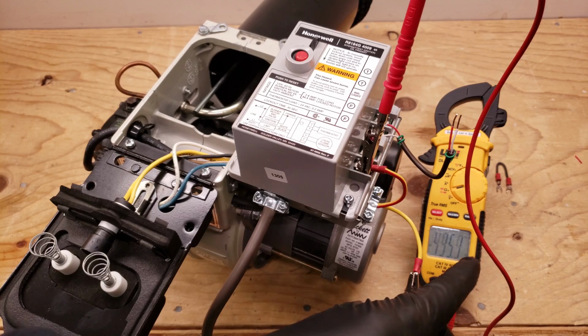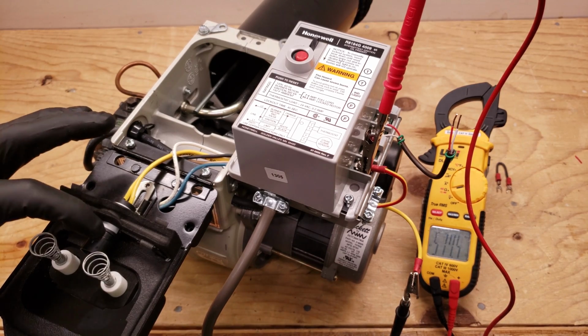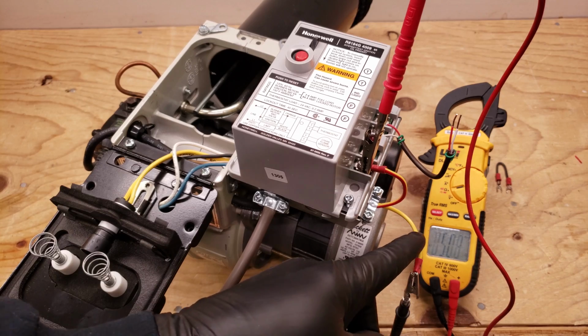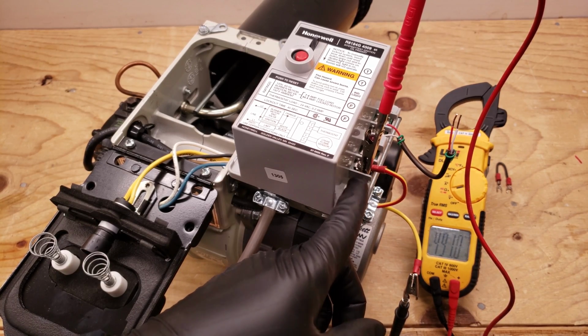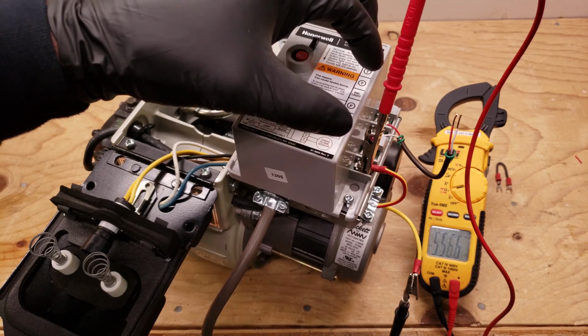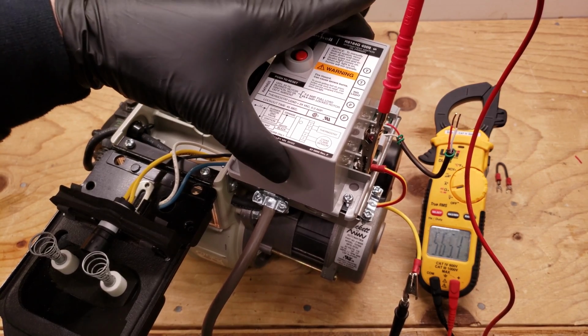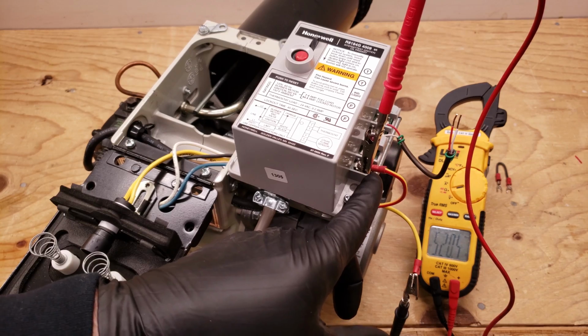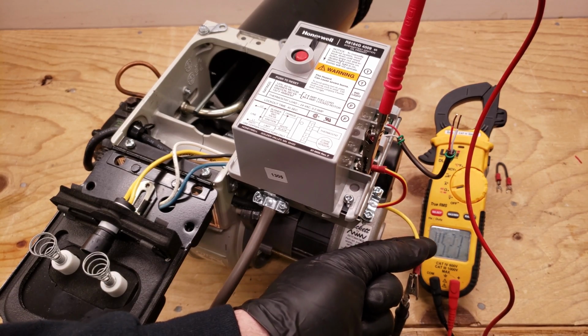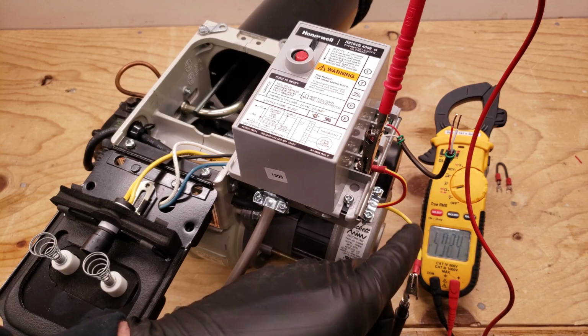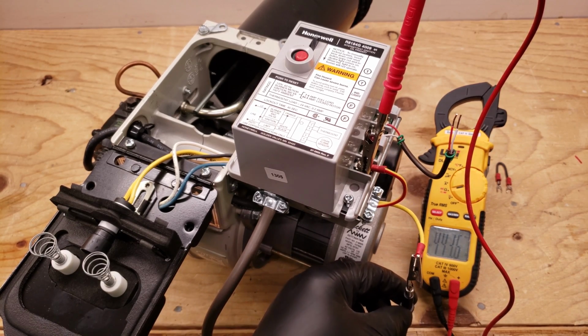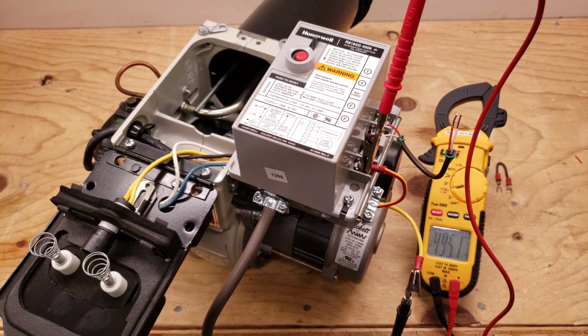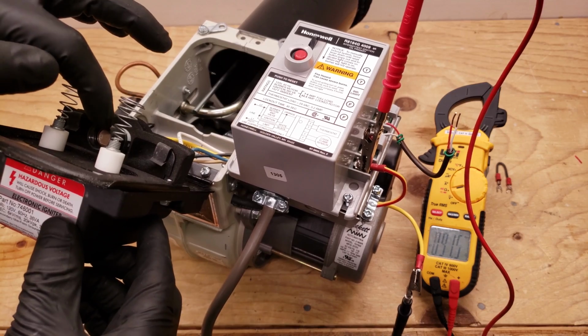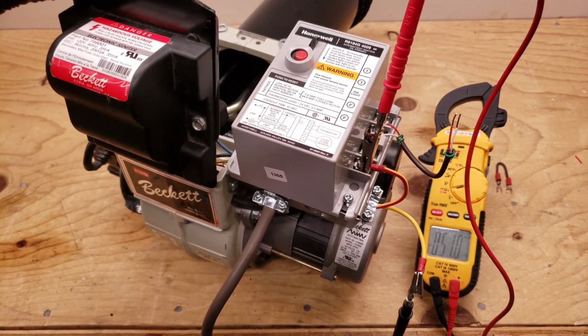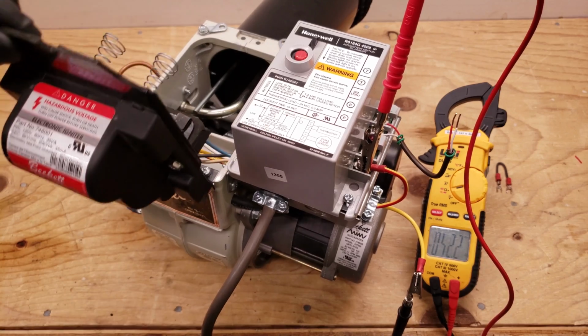So I have my multimeter set on resistance, and I'm measuring the resistance value of this CAD cell. And you see that I have it disconnected from the oil primary control because I don't want to accidentally be reading anything from a control board inside of this primary control. So I just have one alligator clip on the connection here. This other wire going to the CAD cell is disconnected, and it's over here, and I have my alligator clip on that. Right now we happen to be reading a resistance value of about 480 ohms. But that's just because I have this CAD cell exposed to light, and you can see that that resistance value is changing depending on the position of that.